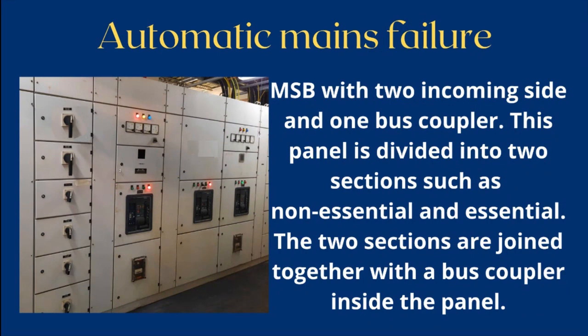This panel is divided into two sections: non-essential and essential. The essential side supplies power to areas where continuous power is required, while the other section supplies the non-essential areas. The two sections are joined together with a bus coupler inside the panel.